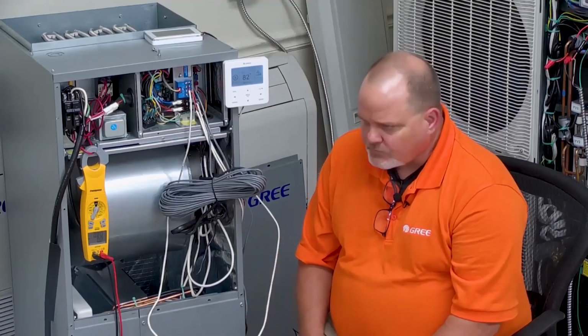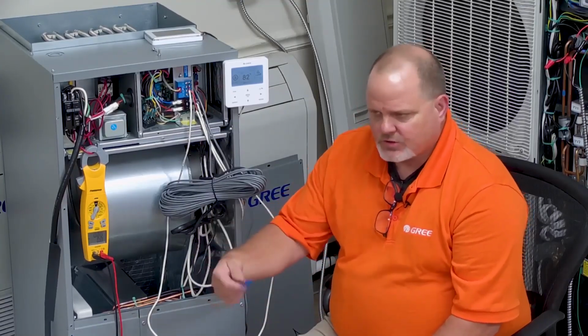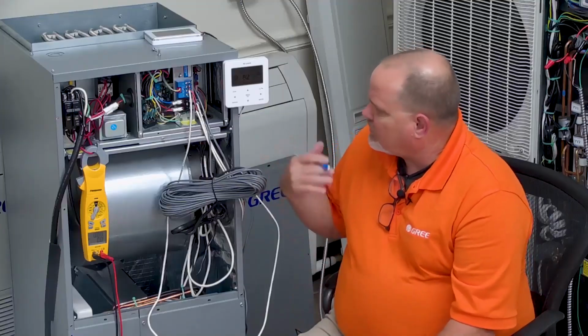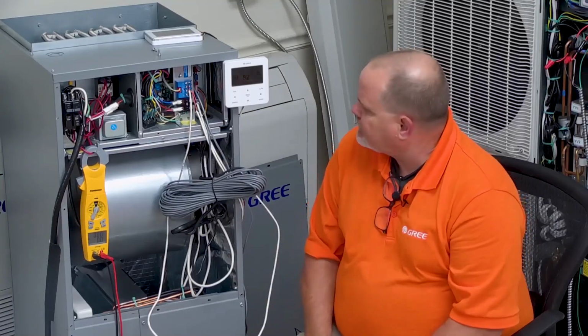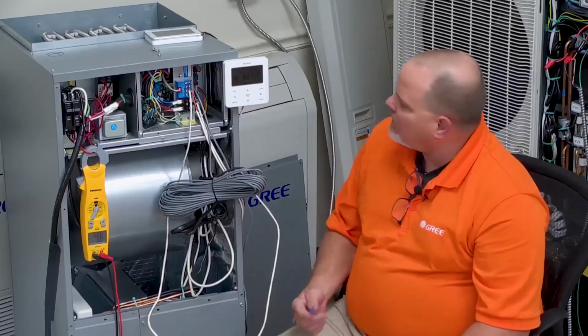What I can't demonstrate for you, or I'm not going to demonstrate for you in this video, is the auxiliary heat function. Because then you got to have the heat pump running, and then the temperature's got to be within a degree or whatever, however the differential we set, and bring on the electric heat as well. The only reason why I'm not doing that, as you can well see here, I don't have this thing refrigerantly piped up yet. So once we get an air handler set up in here and a couple other indoor units, we're going to have a fully functional system where I can run the heat pump and then be able to bring on the electric heat. I will have all that where I can demonstrate it. It does work, I know that, because I got it on my own system at home.